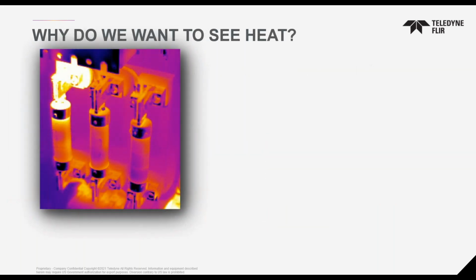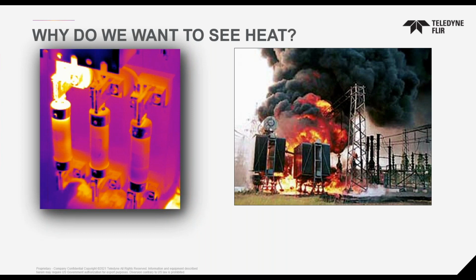This is a picture of a fuse clip with three different fuses, and we have here an identified deficiency with a bad connection. Ultimately these types of situations can lead to significant problems - this is a substation that blew up, usually from insulation issues in transformers, an oil leak, or different gases within the transformer igniting. But really our focus here is predictive, preventative - how do we prevent and predict these types of failures from happening, using thermography as a means to do that, trying to prevent the consequence of failure as much as possible.